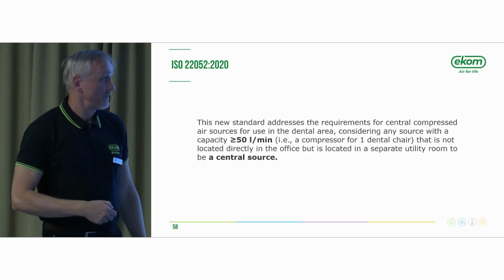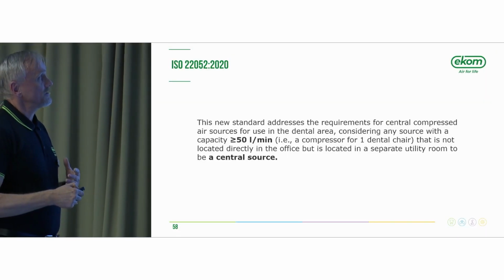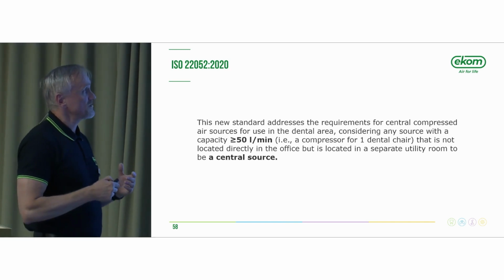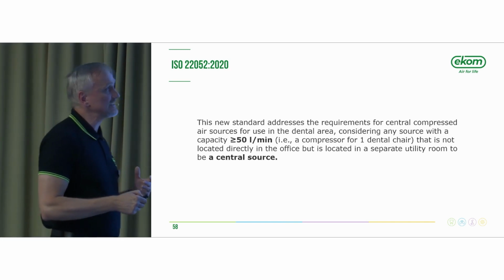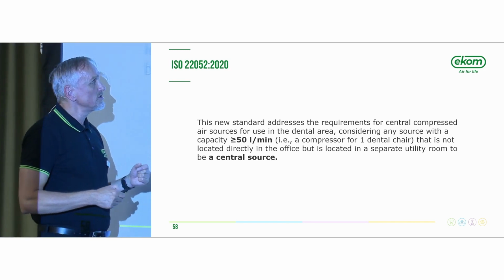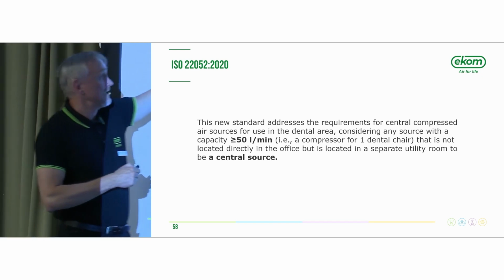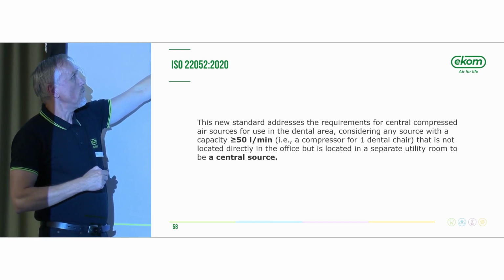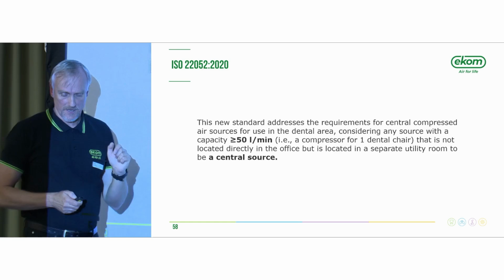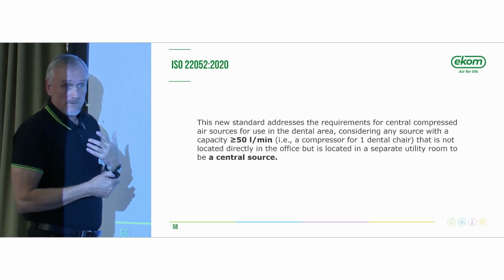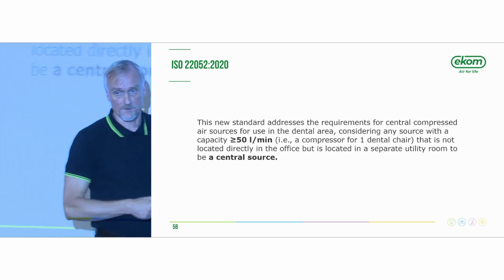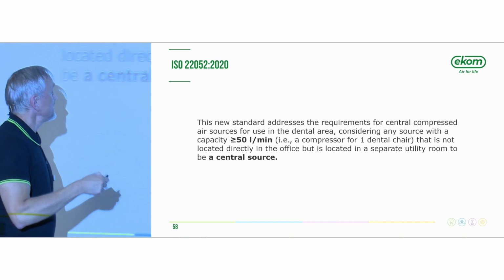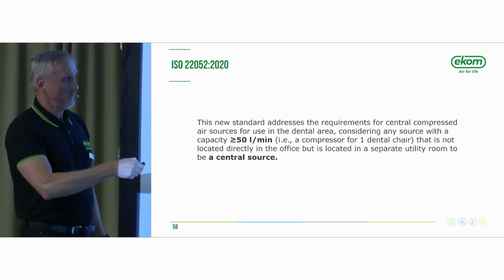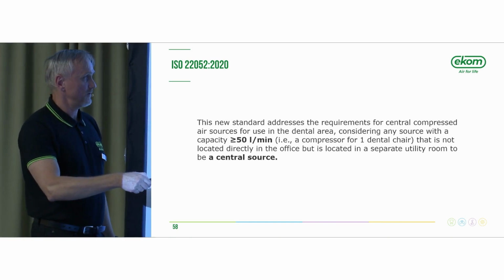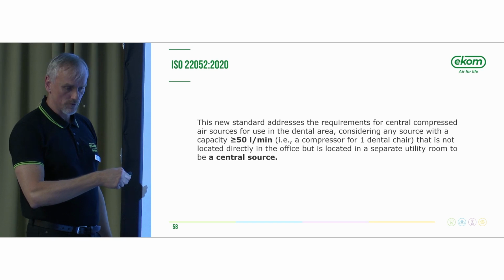Here is the short definition: this new standard addresses the requirements for central compressed air sources for use in the dental area, considering any source with a capacity more than or equal to 50 liters per minute. For example, this is a compressor for one dental chair that is not located directly in the office, but in a separate utility room, making it a central source.